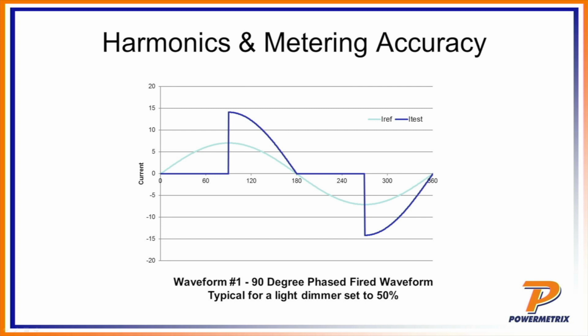The first waveform we're going to look at is called a phase-fired waveform. Here at Powermetrix we refer to this as the shark fin waveform, for obvious reasons. It looks sort of like a shark's fin. This is the current coming out of the load. This particular load represents a good old-fashioned dimming circuit that you might have, say, in your dining room. They used a solid-state device basically to only turn it on for half a cycle, so you're only giving half of the waveform to the light bulb, and therefore it'd only be half as bright.